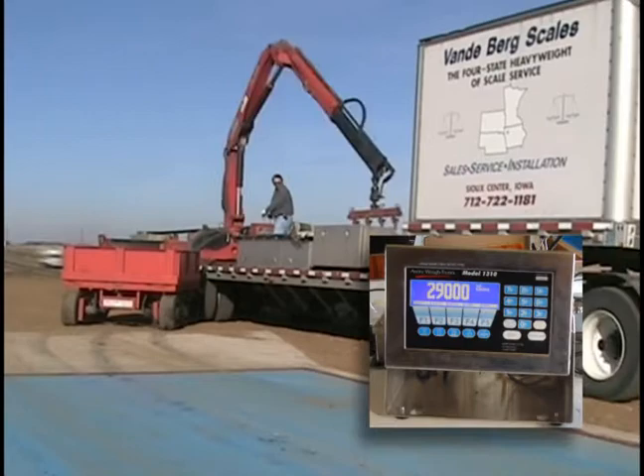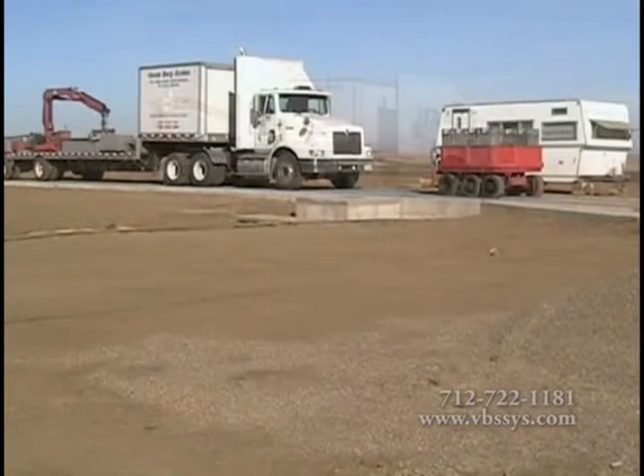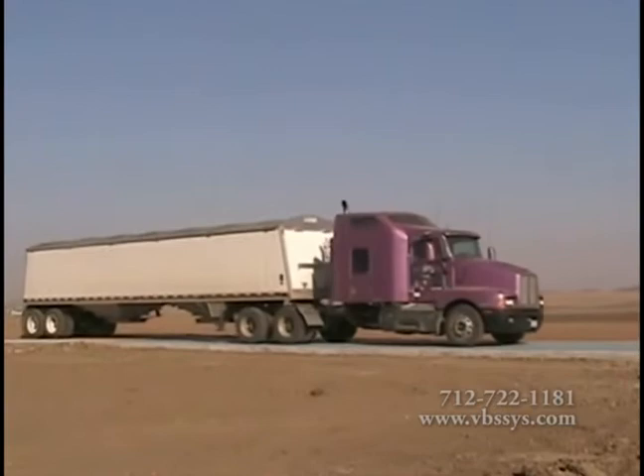The crane then loads the test cart to 29,000 pounds and testing is again conducted on every section to assure accuracy. Vande Berg Scales then performs a stress test on your scale. This test consists of the fully loaded weight cart and the additional weight of the truck to strain test your scale. Once testing is finished, paperwork is then completed, sent into the state, and your scale is now certified legal for trade.